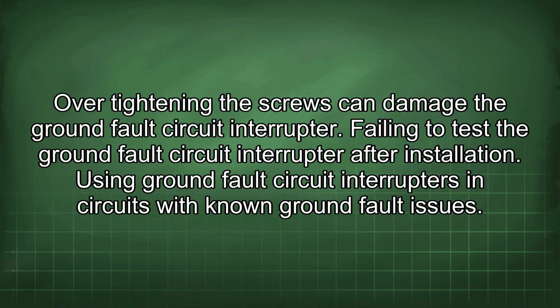Over-tightening the screws can damage the ground fault circuit interrupter. Failing to test the ground fault circuit interrupter after installation. Using ground fault circuit interrupters in circuits with known ground fault issues.